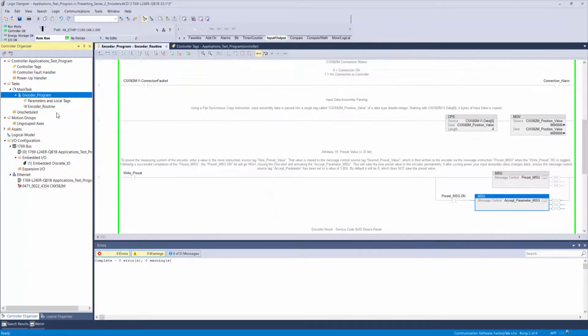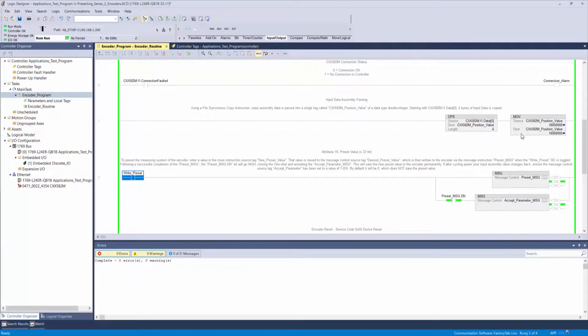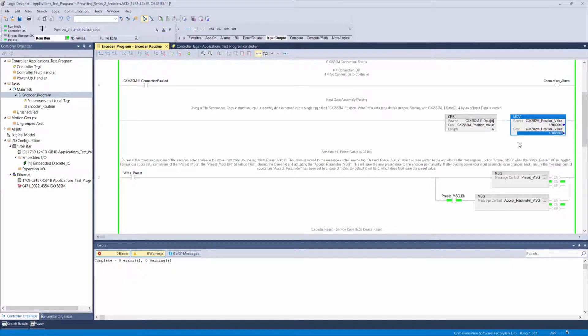In your ladder logic routine, toggle the write preset XIC, and if the message instructions were successful, you will see the done bits go high. Go to your input assembly and verify that your new position has been saved.